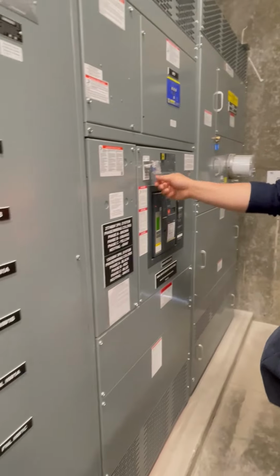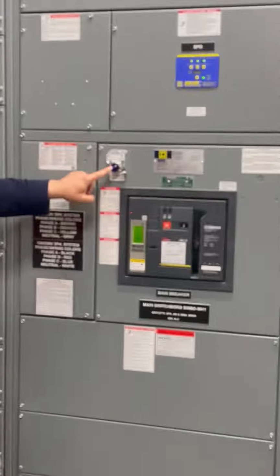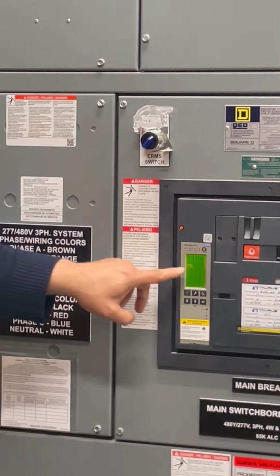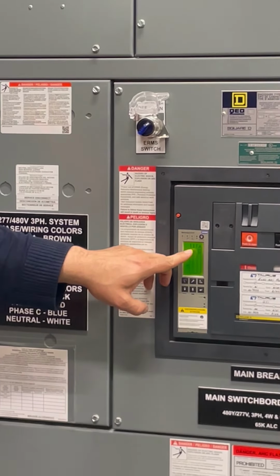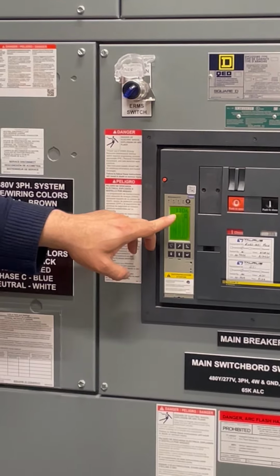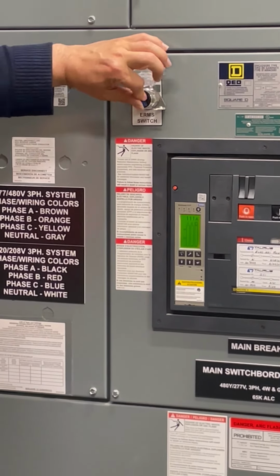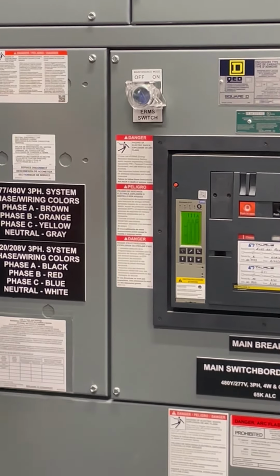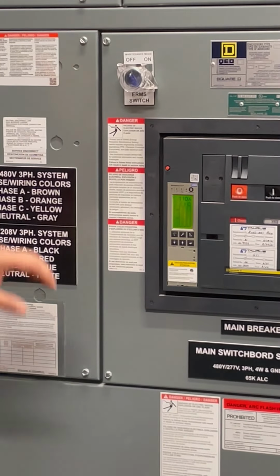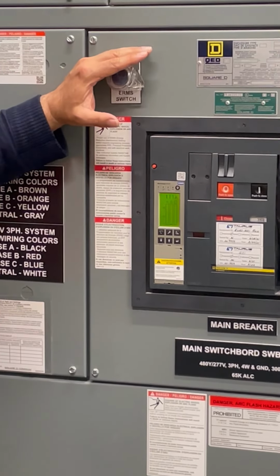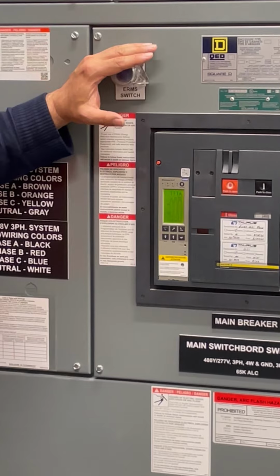The reason, now, when you turn them on, this right here comes blue, and then this right here will tell you it's in ERMS mode, okay? Now, what that does, and what's intended by code, is that any breaker that's 1200 amps and above has to have a means of mitigating the arc flash.